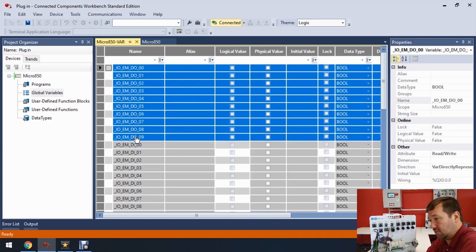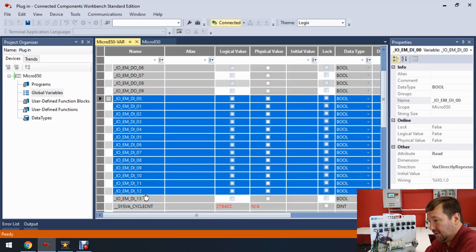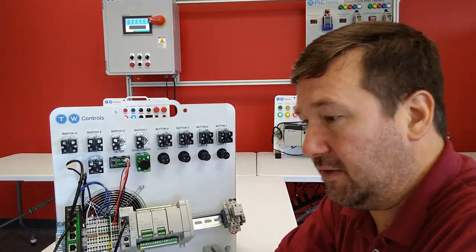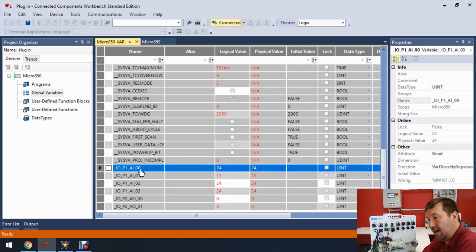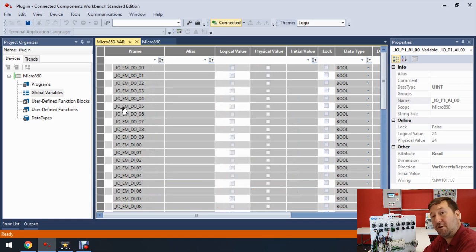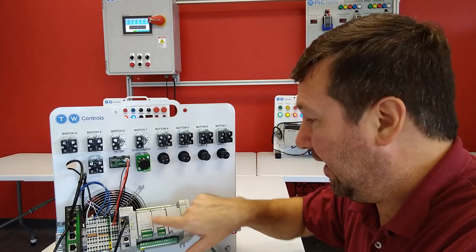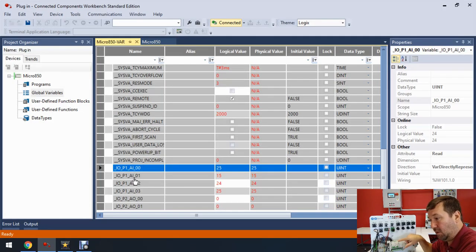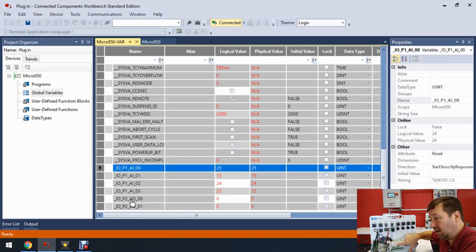We've already covered the basic discrete inputs and outputs. Here are your discrete outputs on the bottom of the Micro 850, and the discrete inputs on the top. If we scroll down, we see new ones: 'IO_P1_AI_00' — where 'IO_EM' was the embedded I/O, 'IO_P1' is plug-in module one. We have analog inputs 0 through 3 since it's a four-point module. Then 'IO_P2' is plug-in module two, with only analog outputs AO0 and AO1.